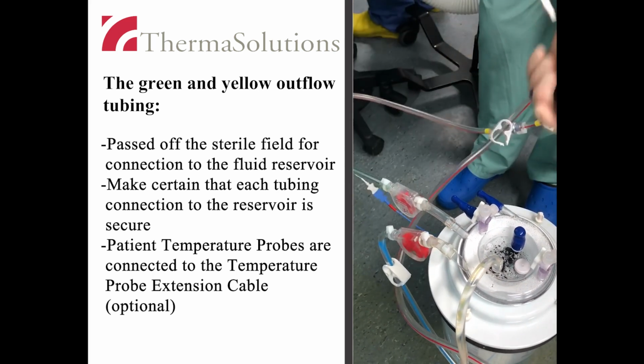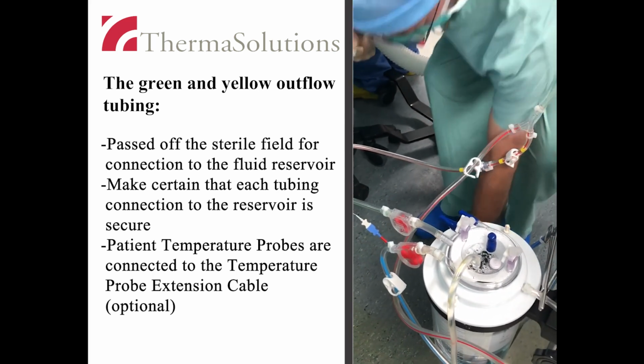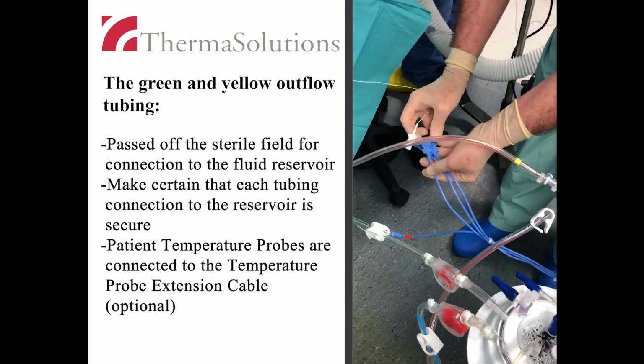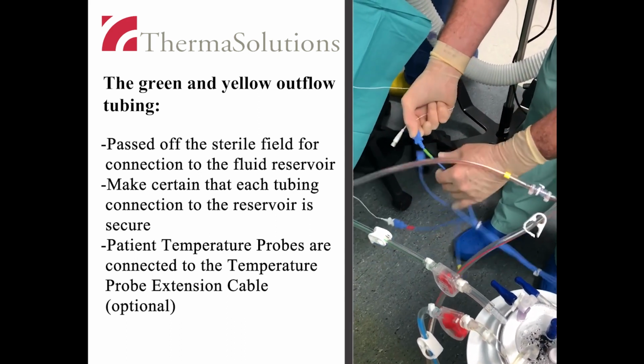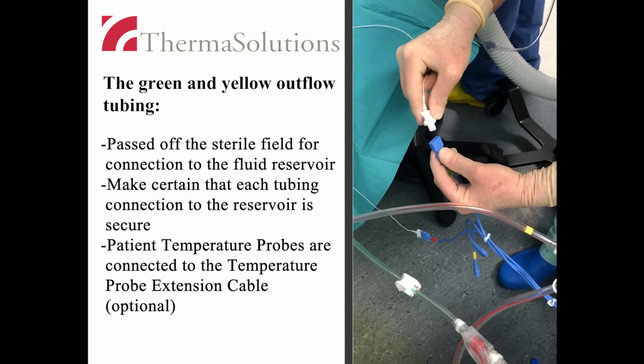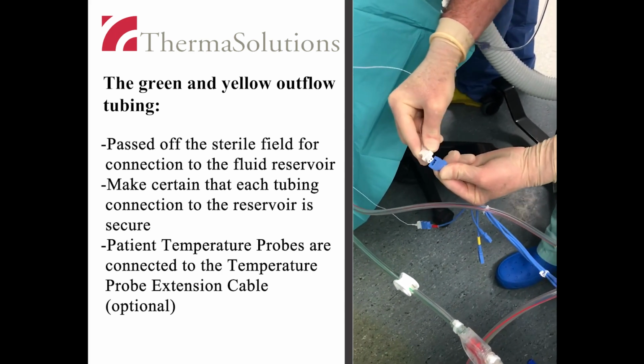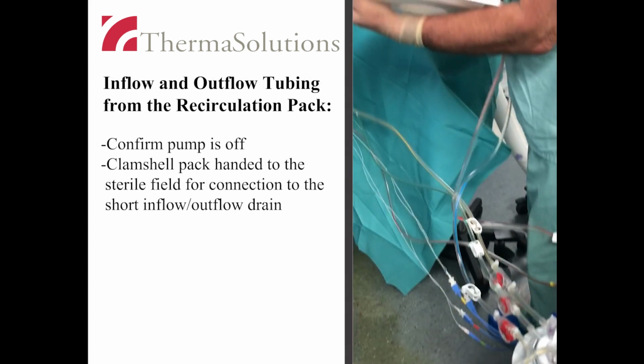The patient temperature probes are connected to the temperature probe extension cables. While not necessary, these temp probes on the blue, yellow, and green tubing can be connected via the extension cables to the corresponding color on the connector panel. Inflow and outflow tubing from the recirculation pack are handed to the sterile field for connection to the short inflow-outflow drain. Again, confirmation that the pump is off should occur.